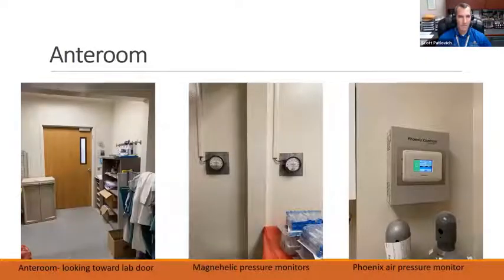You would walk into the anteroom. Please excuse the photos. This is during our annual commissioning. We had some construction activities going on. It's not normally this dirty or dusty, but these are staged pictures during the shutdown. There are magnehelic gauges on the wall that show the air pressure differentials so that our staff can verify that negative airflow is in place before they enter. All the personal protective equipment is located on the shelf that you see here. They would put all this stuff on, or don it, prior to going into the secondary door, which is interlocked to the main entry door so that both doors cannot be opened at the same time.